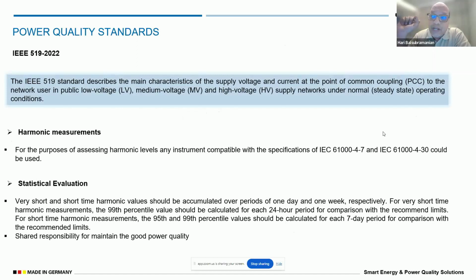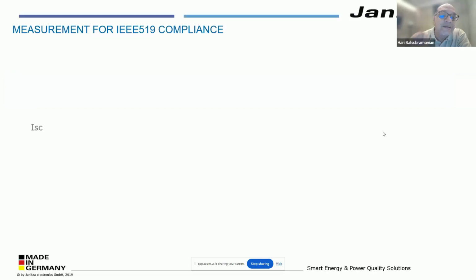For the purpose of measuring harmonics, when you are doing the harmonic measurement for IEEE 519, we need to use only a class A device. This is very clearly defined in IEEE 519. It should be measured at the point of common coupling. That is where the transaction of power happens between the utility and the consumer, and it needs to be measured at that point. And it has to be statistically evaluated on a weekly basis and also on a daily basis. There are limits specified for weekly and daily evaluation in the standard.